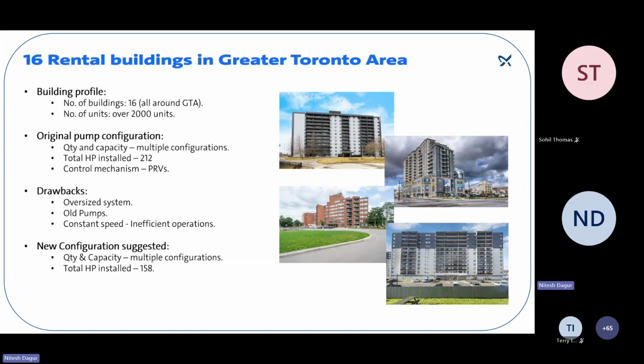Another case study that we have here is with a rental buildings company. We replaced boosters in 16 rental buildings for this single client. The total number of units that were affected were 2,000. The total HP installed was 212, which we brought down to 158. There were multiple configurations, and there were times when we actually upsized the system because of the building needs and the complaints that the customer was facing.